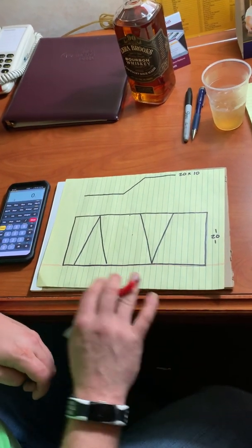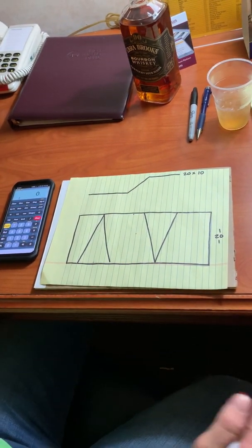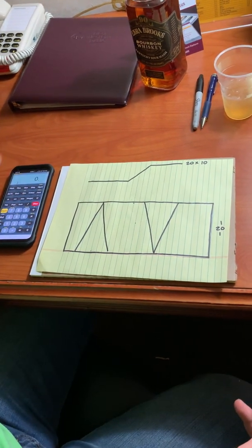The other part about a three-piece offset is you can decide your own angle depending on how short or long you want this offset to be, or how many pieces of duct you want to do it in, or how tight the offset has to be smashed into place.